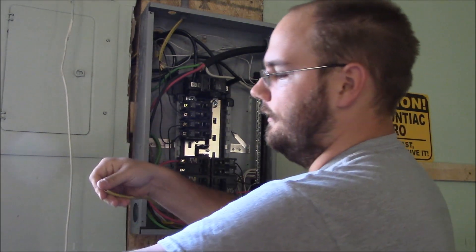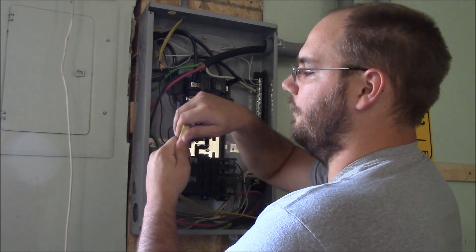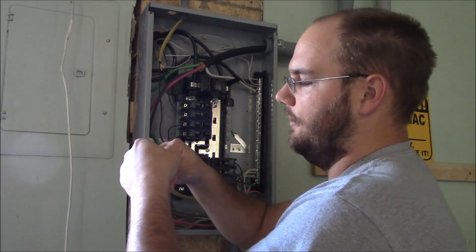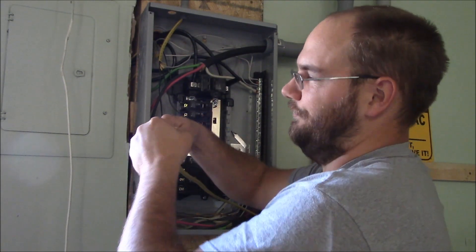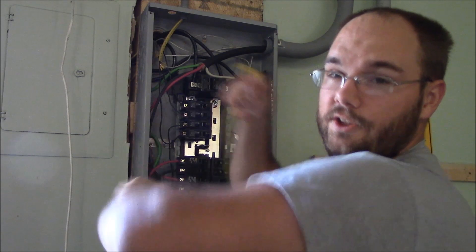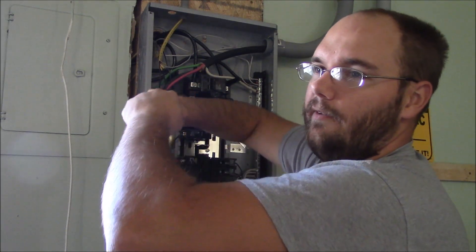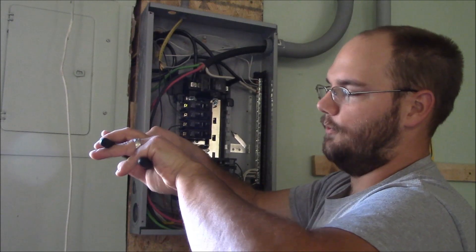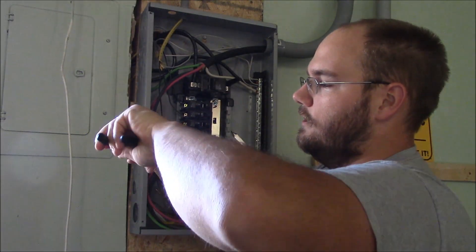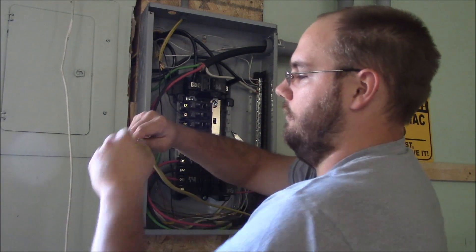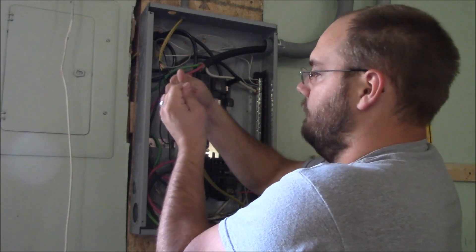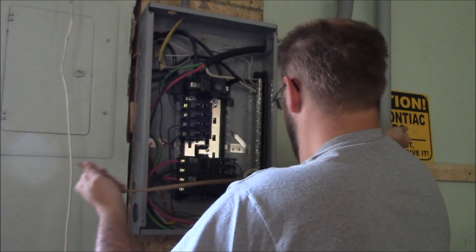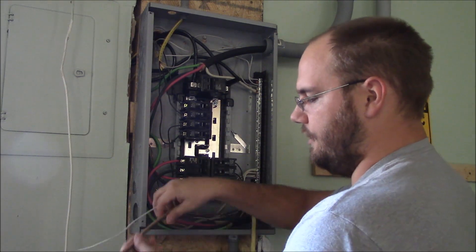Just to start taking off this insulation, this outside of the cable here. This is a 12 gauge, so it's a little bit heavier. I like to use 12 gauge—not necessarily that you can get a little bit extra load in it, but it's a pain in the butt to work with. But it is a little extra security in my mind, I guess. And also on the shop here, if I have plugs where I'm going to be plugging in a welder, then I'm going to need that 20 amp breaker minimum for that. So you just start and then you strip back the cable sheath, get some of this paper insulation out of your way.